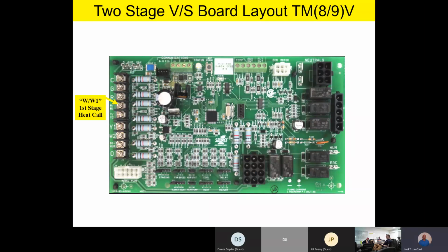Now, team, if you have a two-stage heating product, we always recommend that you make sure and put a two-stage thermostat on there, for the ultimate comfort and because it's going to give you the most functionality. But we also know in the field, sometimes you're just stuck with what you have. So if you are stuck with a single-stage thermostat, be sure and land it on that W/W1 wire for that first stage heating. Y/Y2 is going to be our second stage cooling call. Again, this board is actually set up for a two-stage heat, two-stage cooling operation. Y1 will be our first stage cooling call if you have a two-stage product outside.